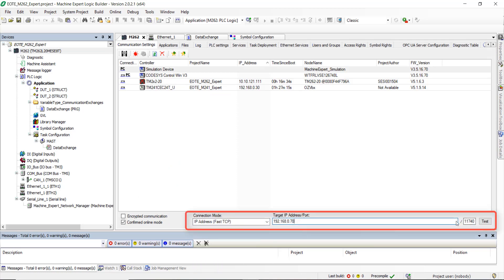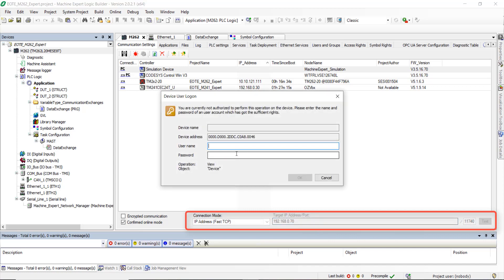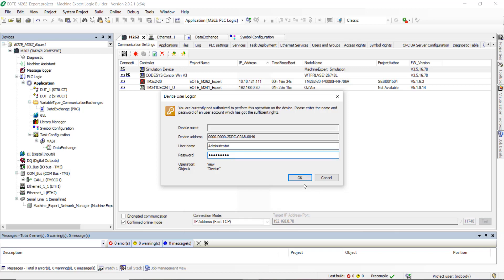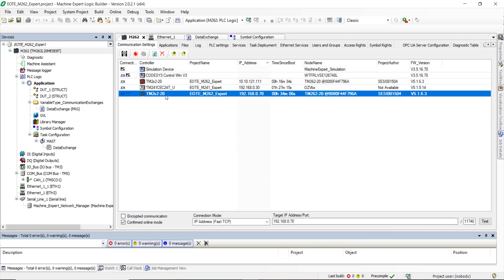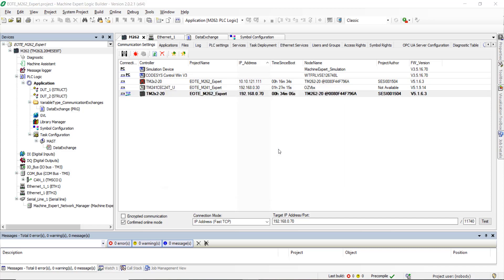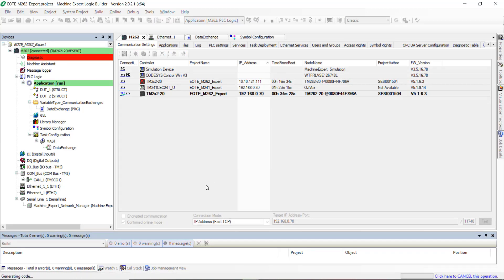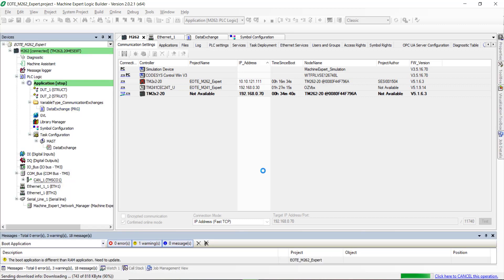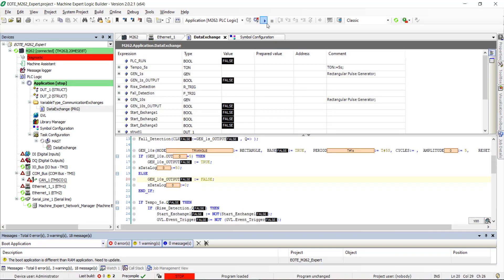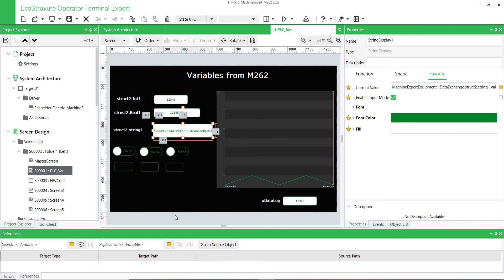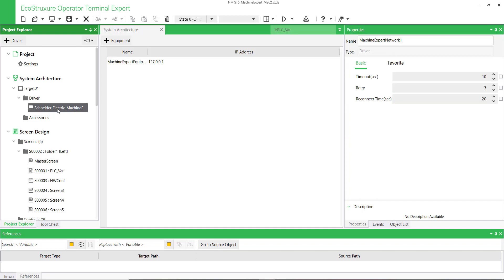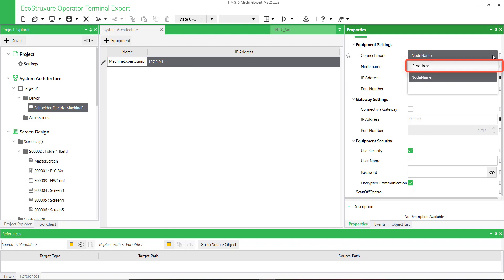With the M262 PLC, the connection has to be done in Fast TCP mode by using port 11740. Select the right PLC and download the application into the PLC. Now switch to EcoStruxure Operator Terminal Expert to configure the driver. Click on Machine Expert Equipment and display the equipment settings. Select IP Address — M262 supports only IP Address as connection mode.